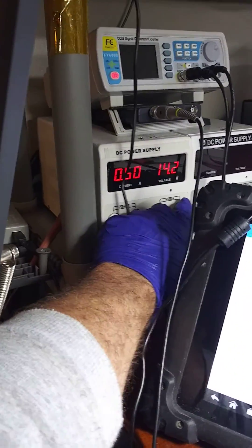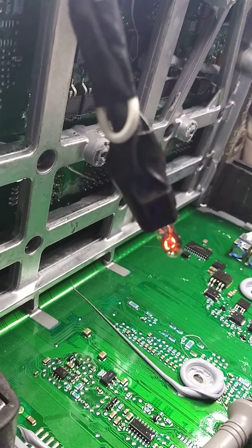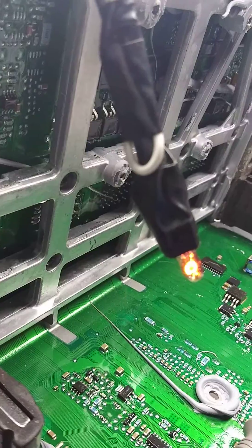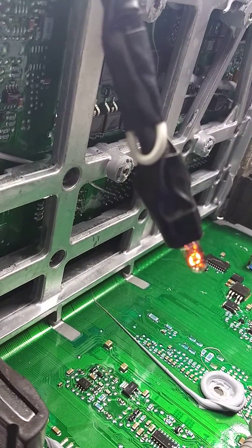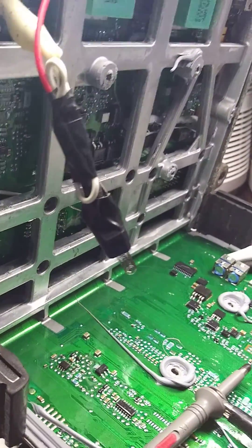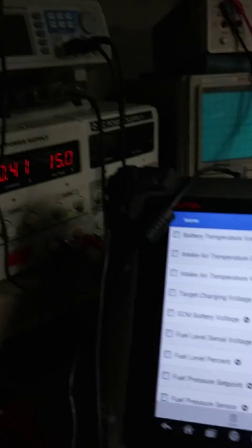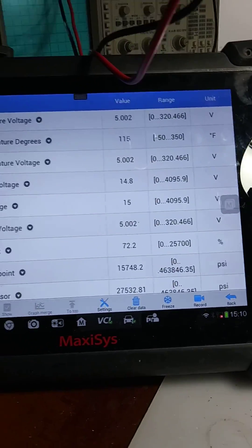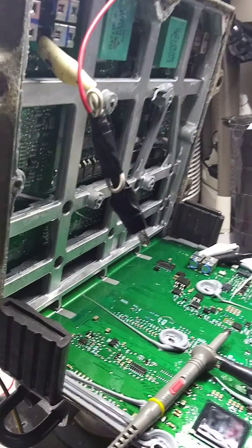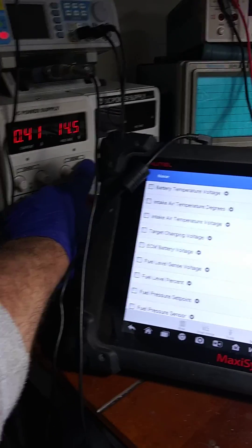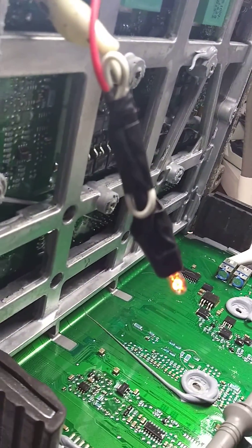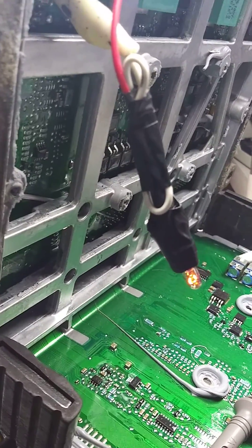If we turn our voltage up to 14.9, we'll see it turn off. It's hard to get that exact — I have it at 15 — but we can see that it's turned off now. And then if we come back to 14.5, it turns back on.